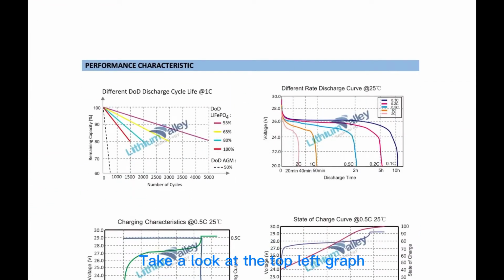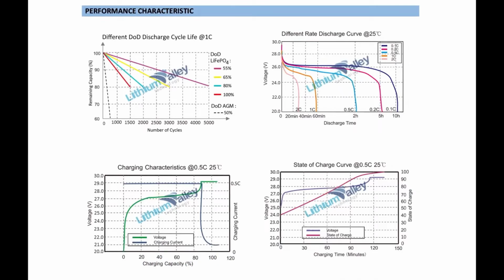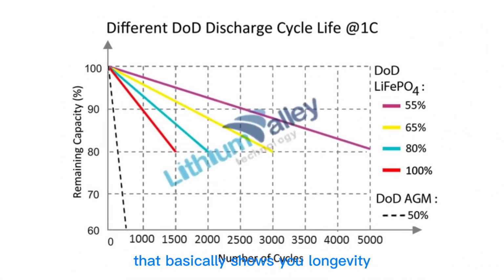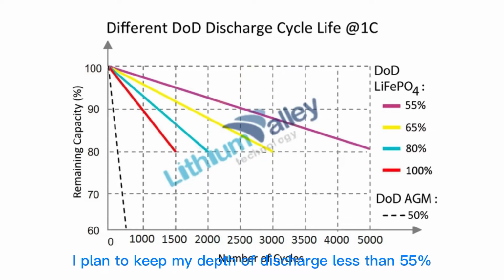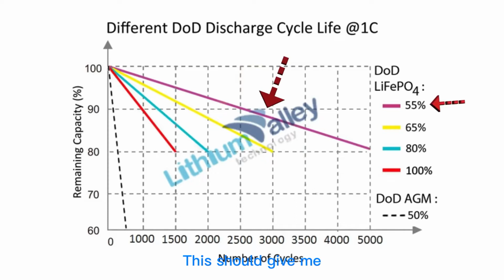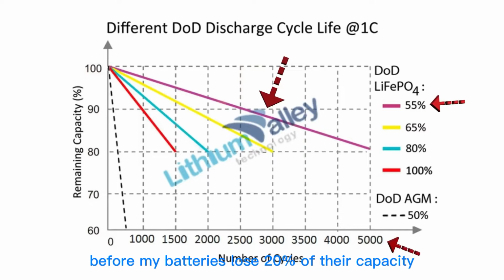Take a look at the top left graph. That basically shows you longevity. And longevity has a lot to do with your depth of discharge, how deep you discharge your batteries. I plan to keep my depth of discharge less than 55%. This should give me 5,000 cycles before my batteries lose 20% of their capacity.